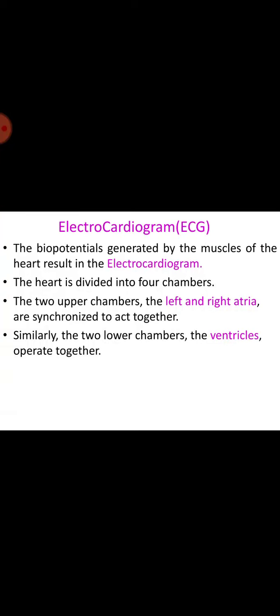Welcome to this module. In this presentation, let us have an insight into the electrocardiograph. The electrocardiograph is an instrument which records the electrical activity of the heart. The potentials produced in the individual fibers of heart muscle are added to produce the ECG waveform, and an electrocardiogram is the recorded ECG wave pattern.